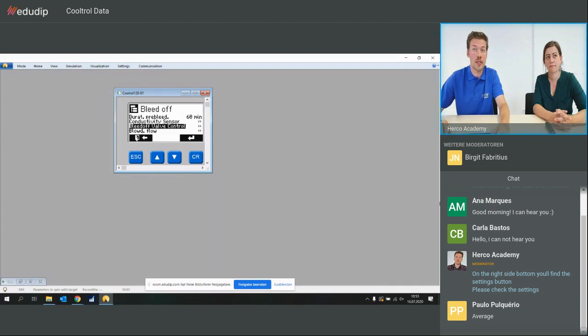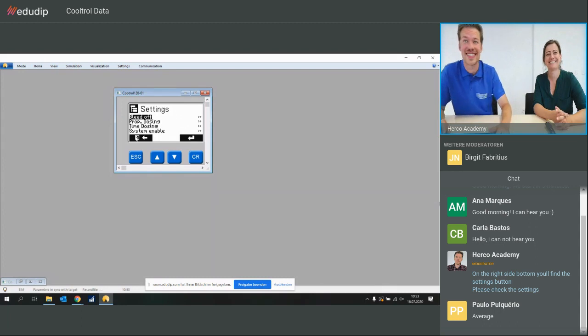Right, so if we continue, we have all the information for the valve control. So this is actually for telling if it's normally open, normally closed. For the flow sensors, we have the information about how many impulses we are having. So this is basically interesting for you if you're using your own flow meters inside. So we get the correct information from the flow sensor.